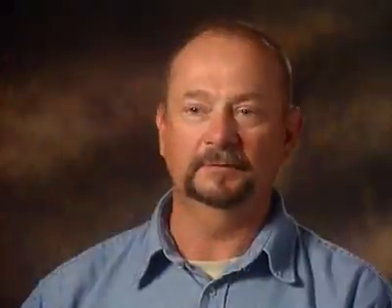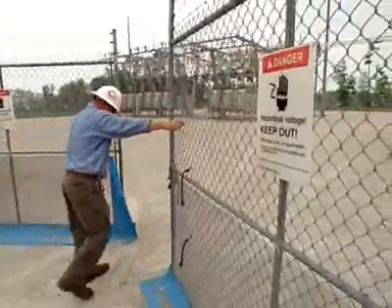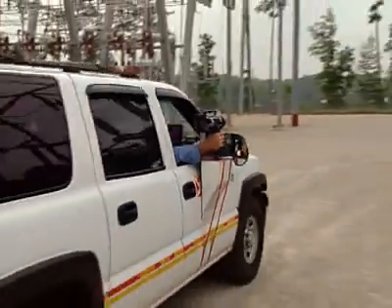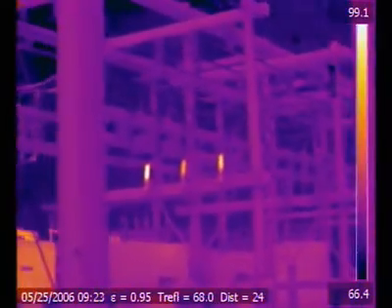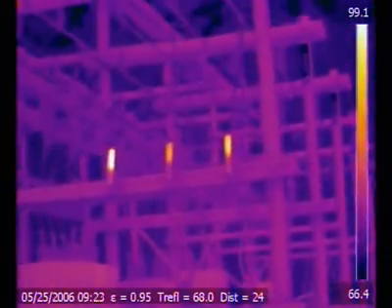With the infrared camera, you can cover a whole broader area — you can go in and do a whole section. When I drove into the substation today using the new P640, the resolution was awesome. Seeing some hot spots showing up over here on the right. As soon as I drove in, the arresters were just there. I didn't have to look for them — they just appeared in the camera.